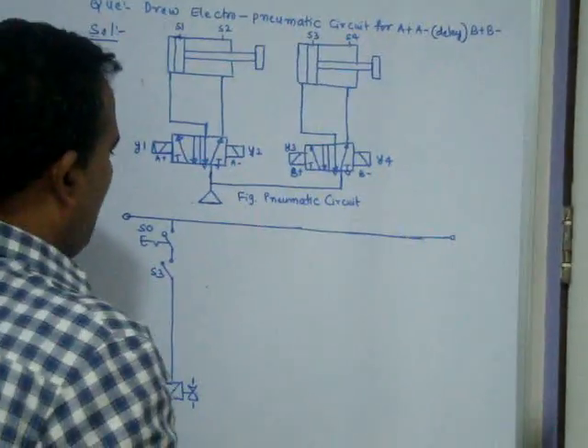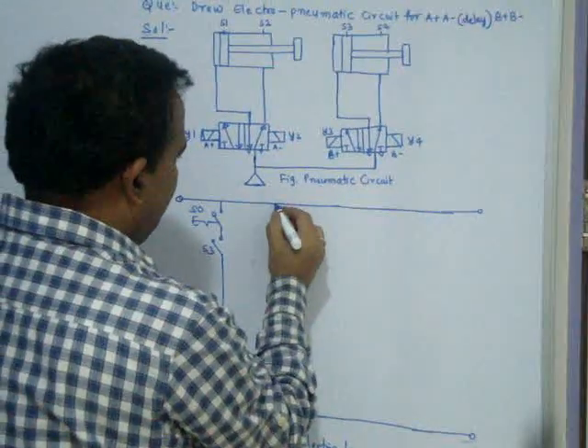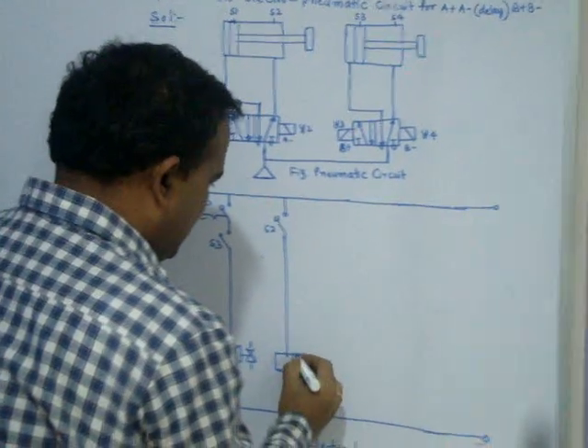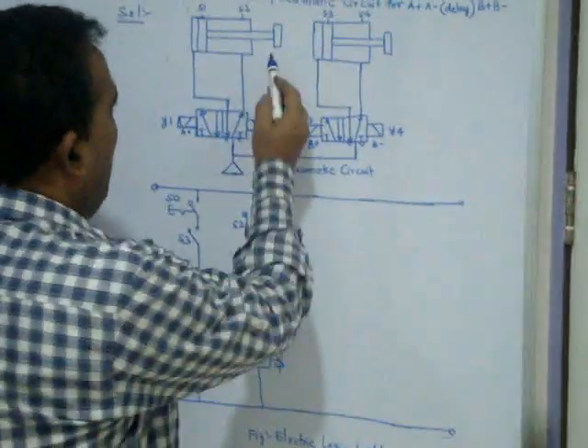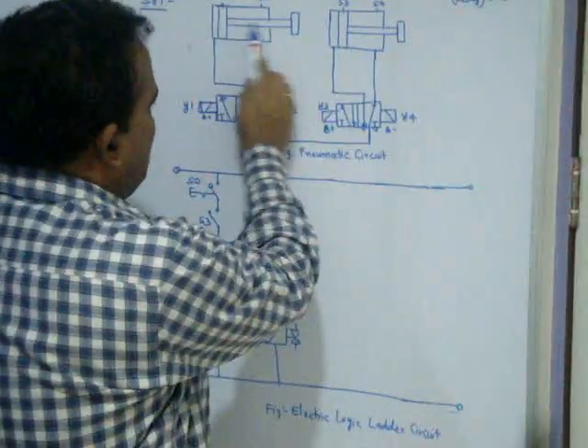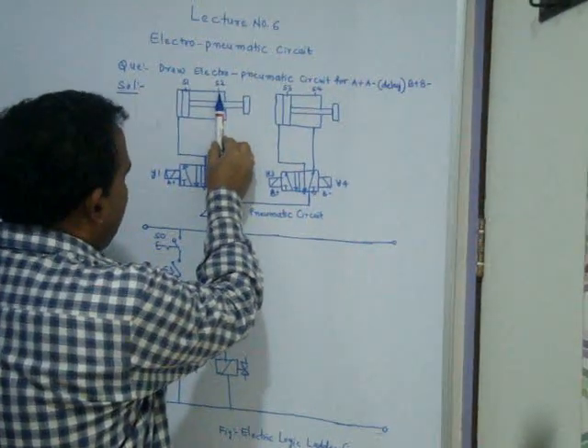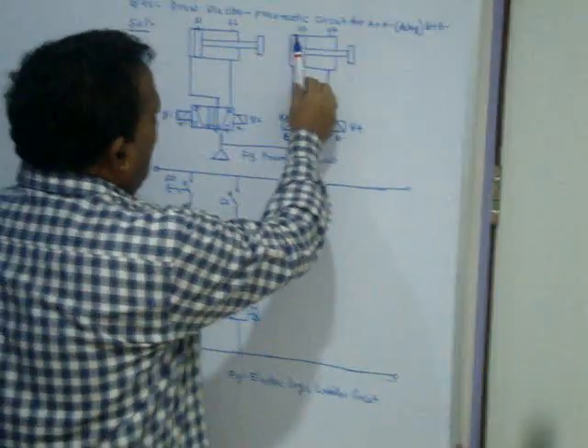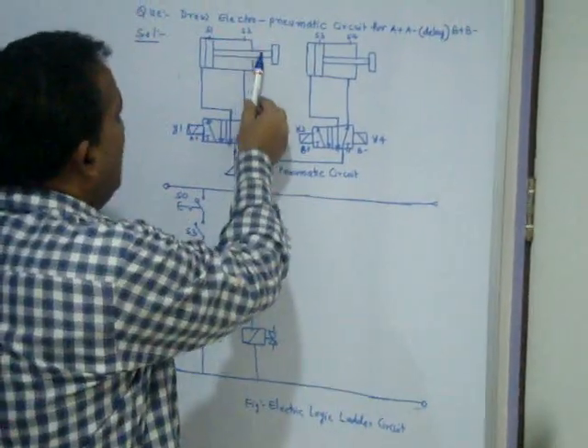When the piston goes to S2, A minus should happen. A minus is nothing but Y2. When it comes back to S1, already S3 is on, and the piston goes to S2 again. If I draw only these two electrical logic lines, the piston just oscillates between S1 and S2 — the second cylinder is not moving at all. So I need to stop this oscillation after one stroke. To prevent this, I must add S2 as a condition so that after reaching S2, the circuit doesn't keep repeating.